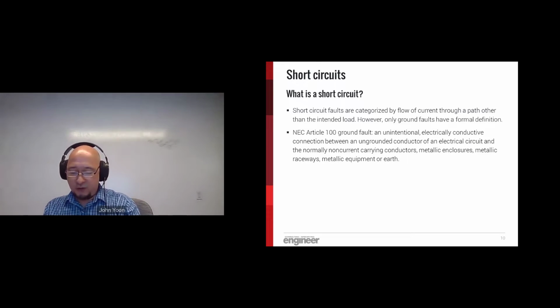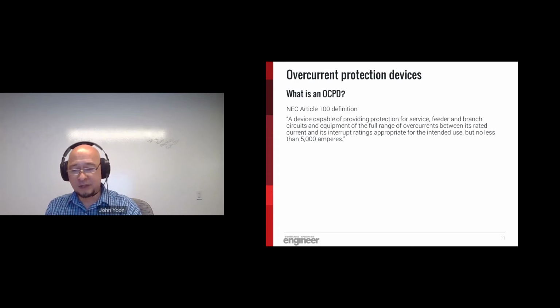Faults or short circuits, on the other hand, are where current flows through a path other than the intended load or circuit. Oddly enough, the NEC doesn't formally define all types of general faults or short circuits. Only ground faults are defined within Article 100. The ground fault definition is indicated on this particular slide that you can read yourself. Give you a second to take a look at it, and let's move on to the next one.